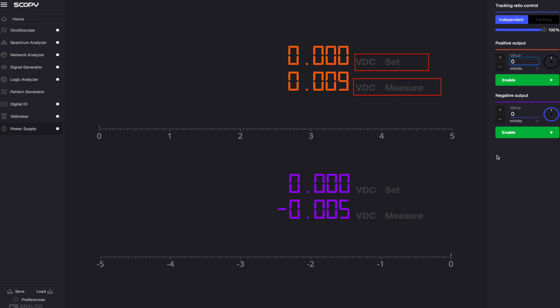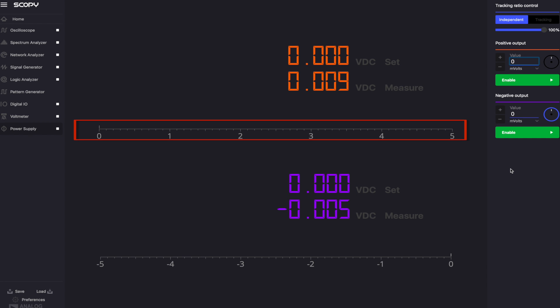For the positive output, the two orange digital indicators represent the value in volts currently being set and the value in volts that is measured back. For the negative output, these indicators are purple. Below each indicator pair, the measured value is graphically displayed on a scale.